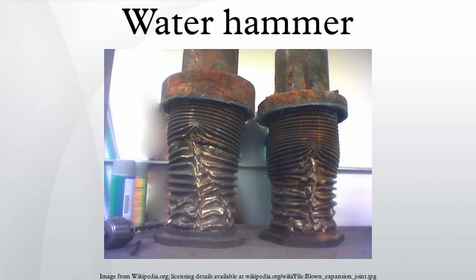Subsequently, steam picks up the water, forms a slug, and hurls it at high velocity into a pipe fitting, creating a loud hammering noise and greatly stressing the pipe. This condition is usually caused by a poor condensate drainage strategy.